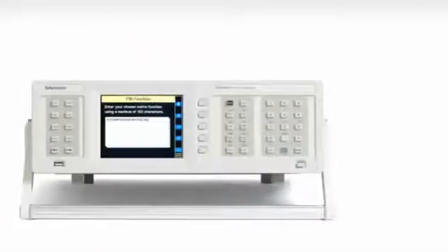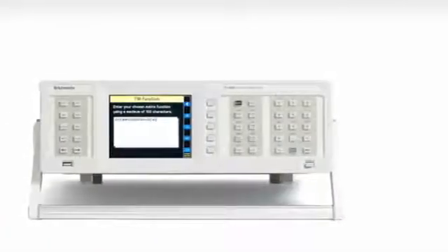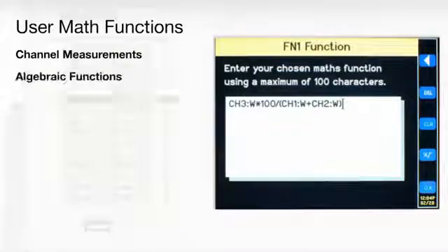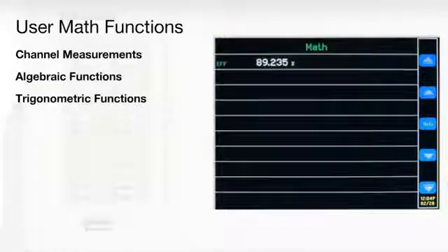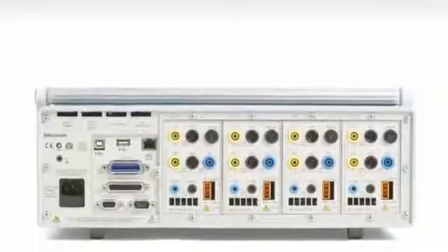Complying with efficiency standards like ENERGY STAR and others is increasingly important. With the PA-4000, you can define up to 30 math expressions, combining multiple measurements to calculate efficiency as required by the standards.